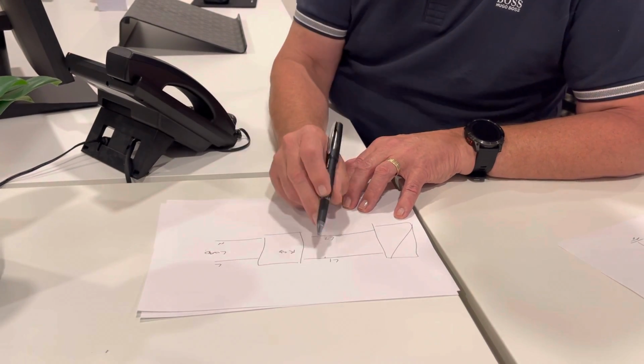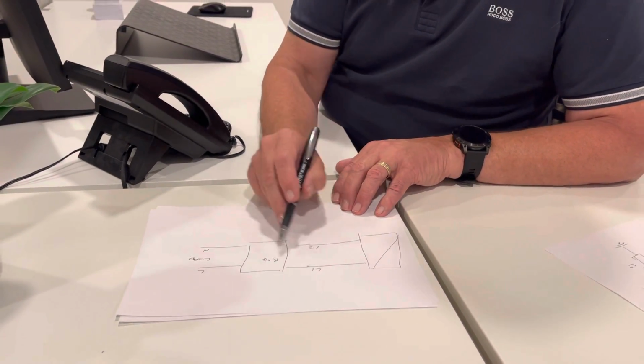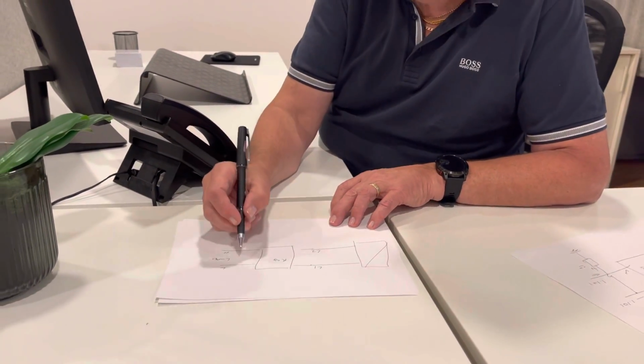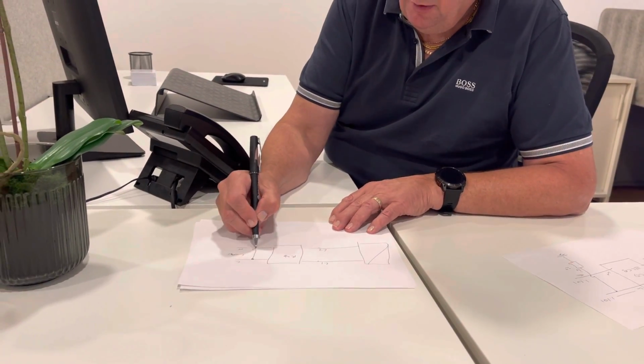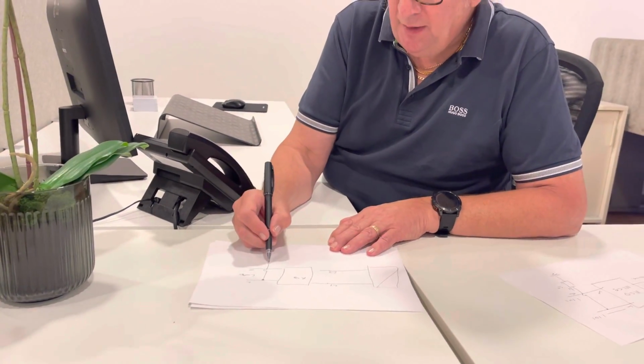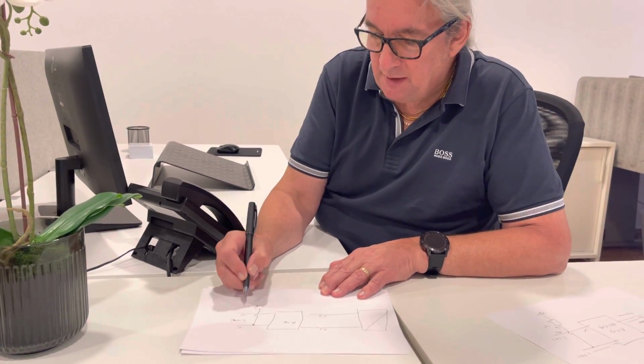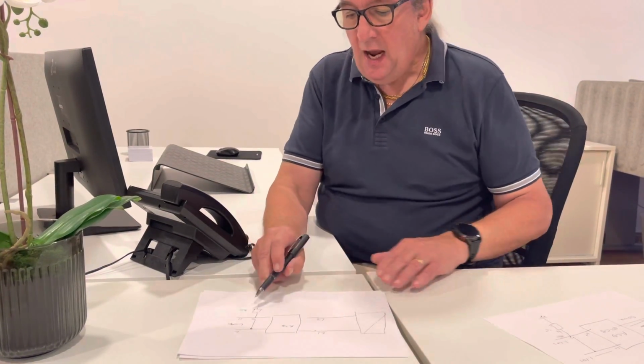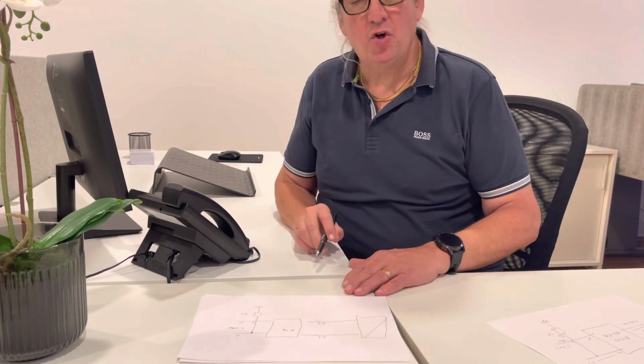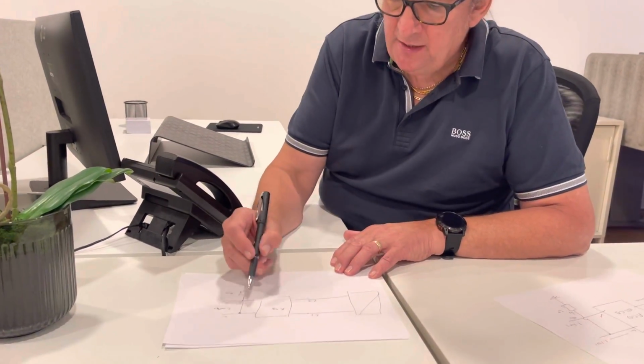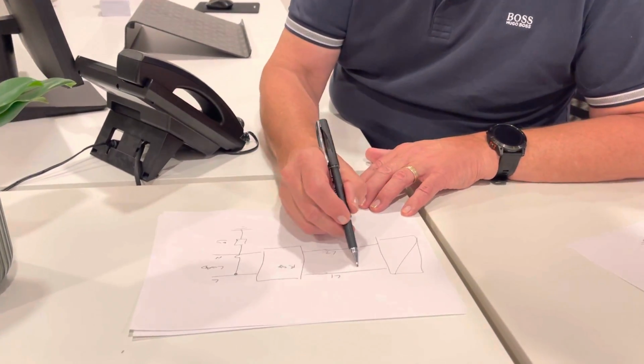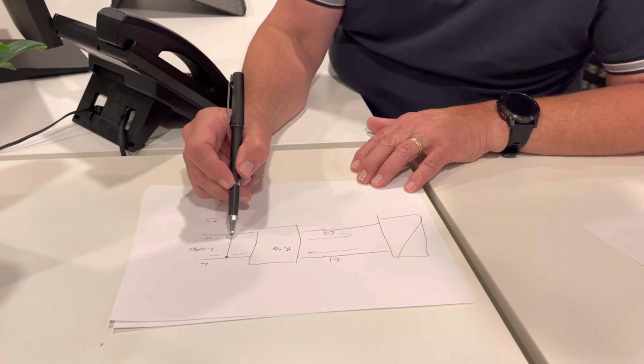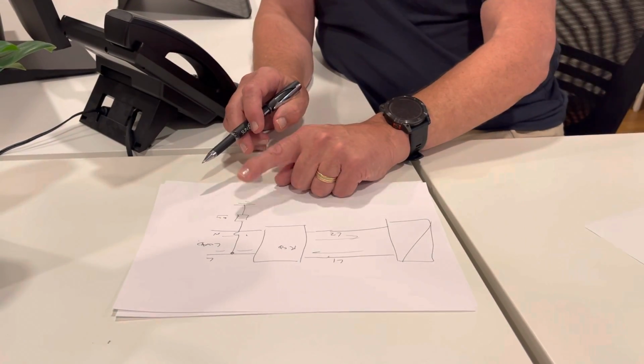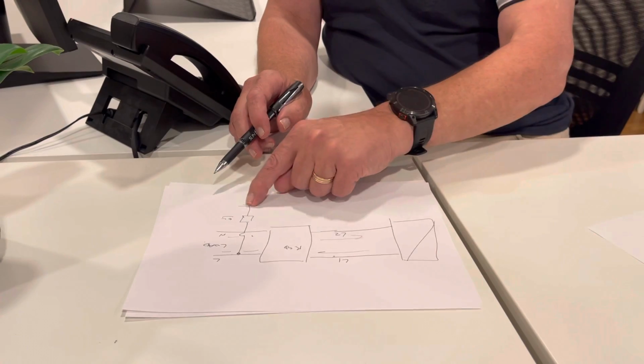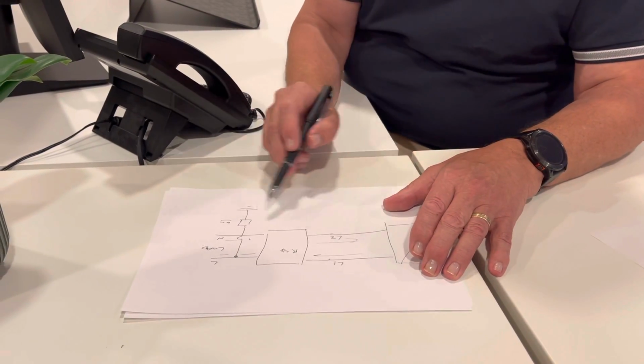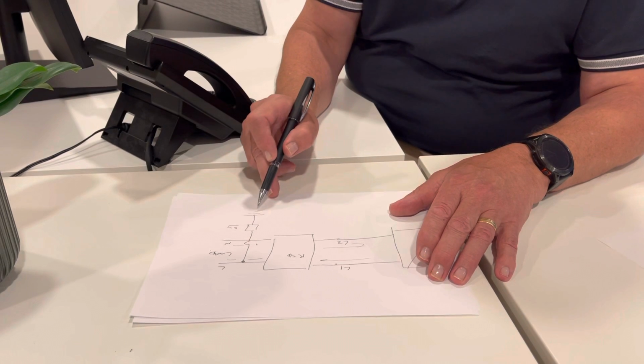But in fact, these are balanced. And these are basically like an isolated mains. If I'm to touch here, I'll just use the live wire, and I put the resistance, which is me, it's my smiley face, and there's the ground here. I'm touching the live here. This cannot trip, because this device is measuring what goes in and what comes out. Because when I touch the ground here, these aren't referenced to this. This has to have a power flow. So if I was to touch here, the energy can't flow here.